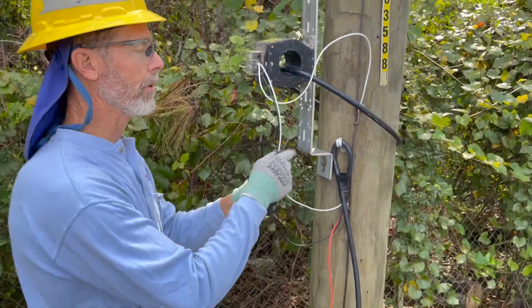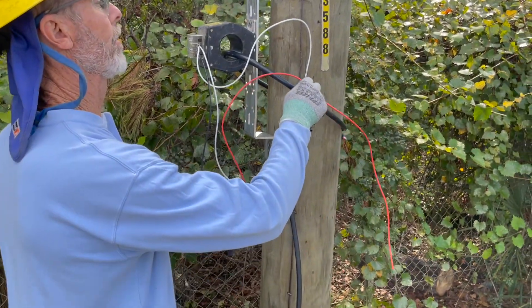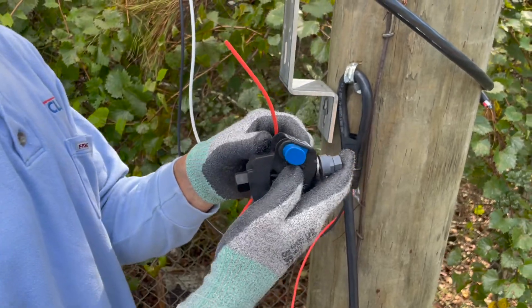The next thing: we have our currents wired, so now we've got to hook up our potential. To hook up our potential, we want to go to the high side on the end coming from the transformer and hook up our potential pole. Now we're going to hook the piercing connector to the pole.